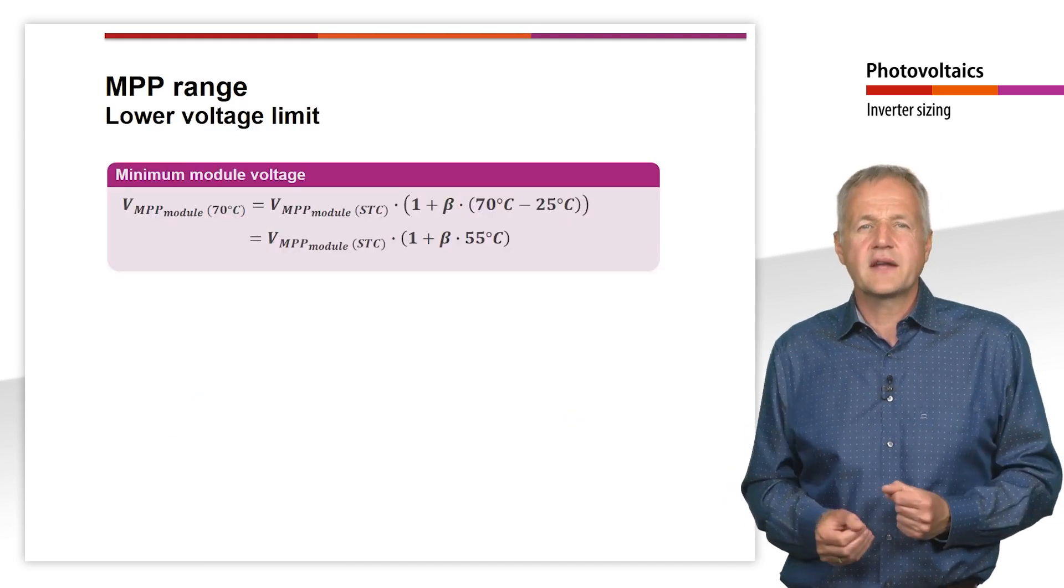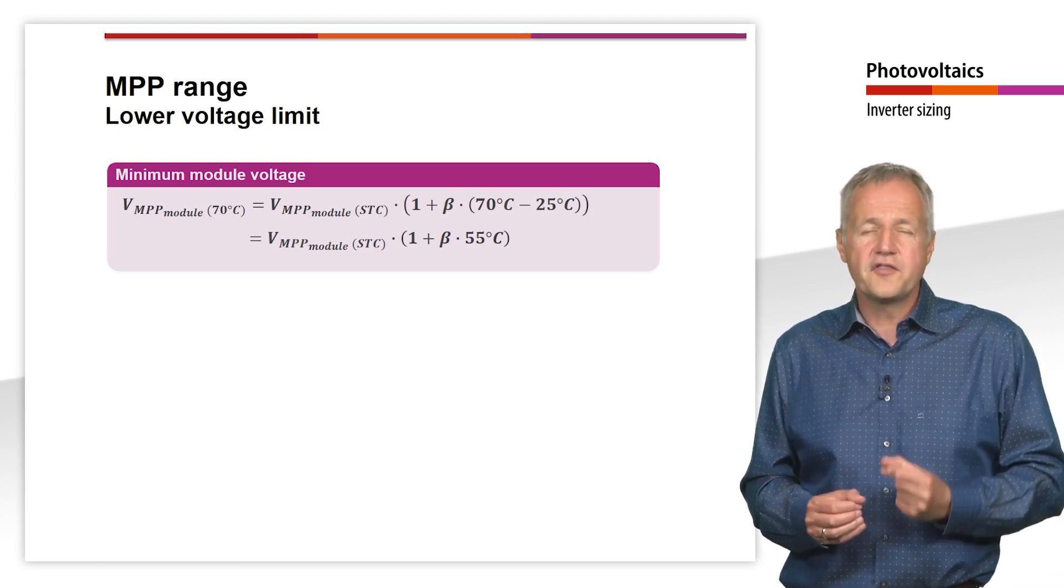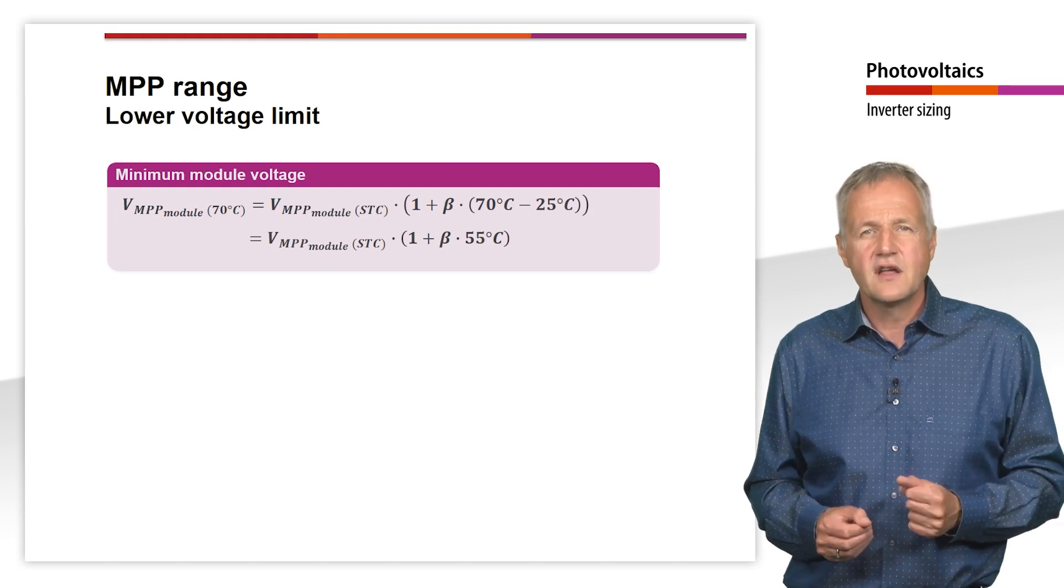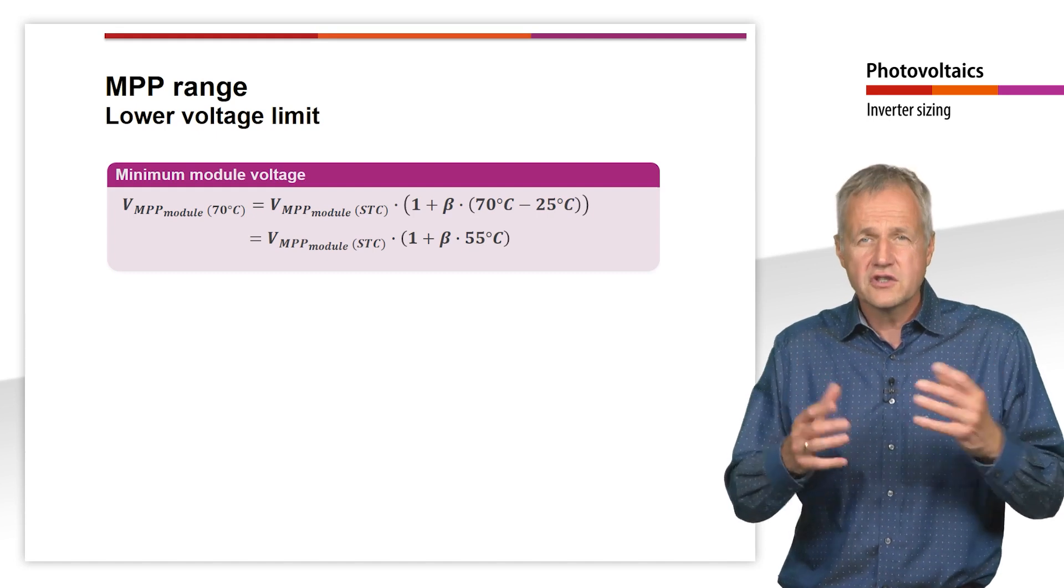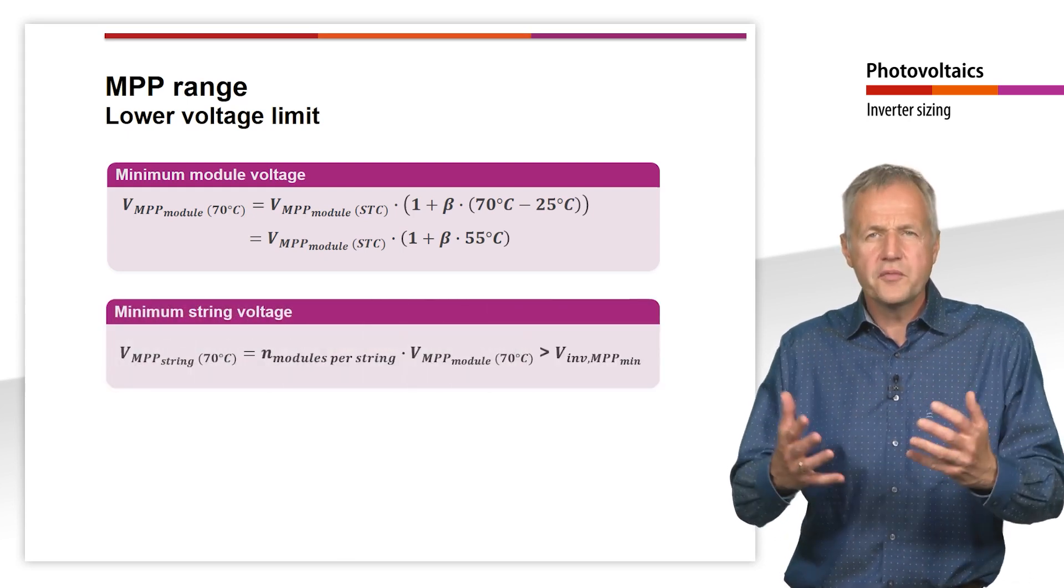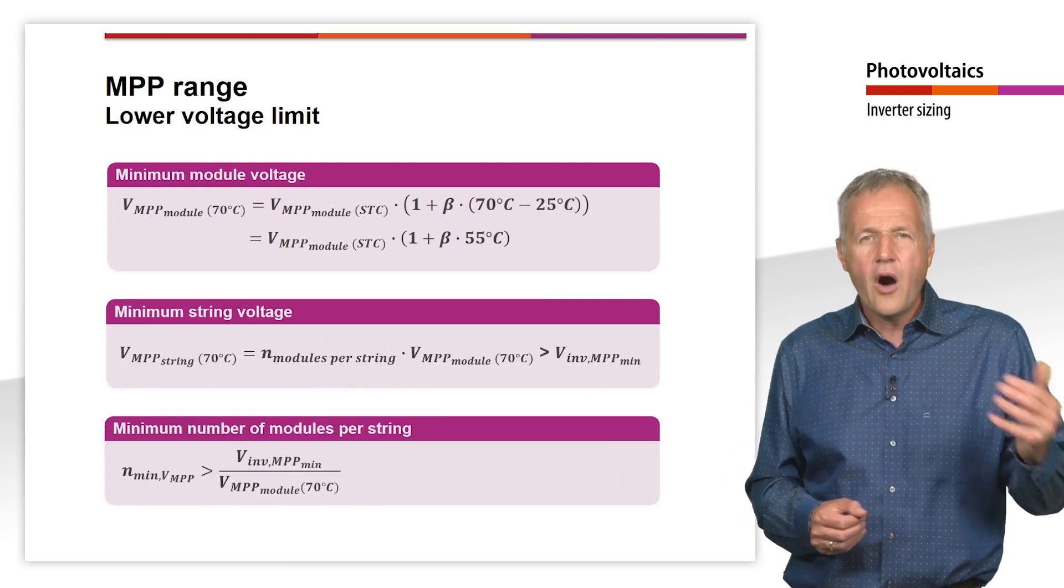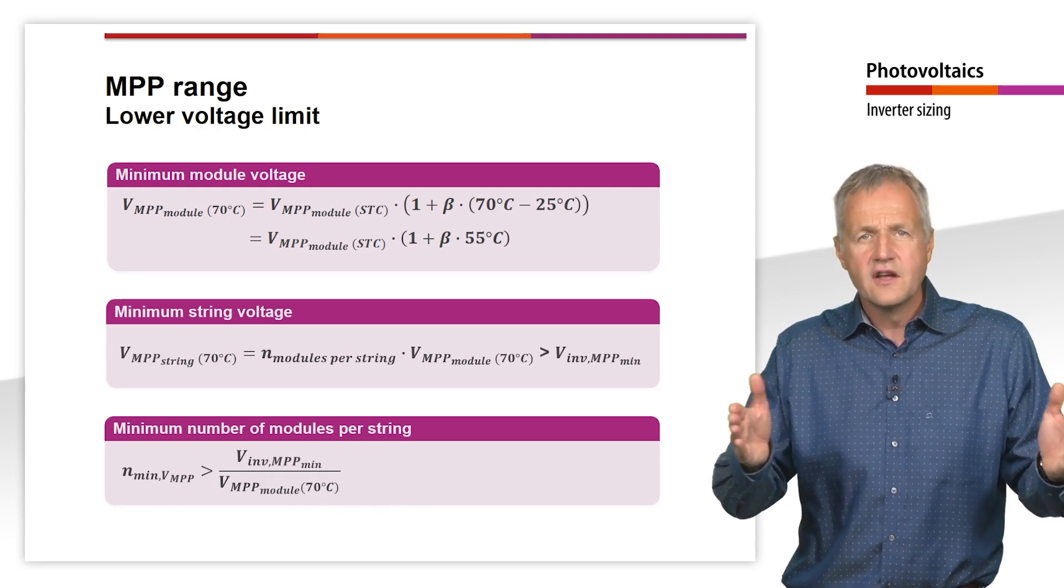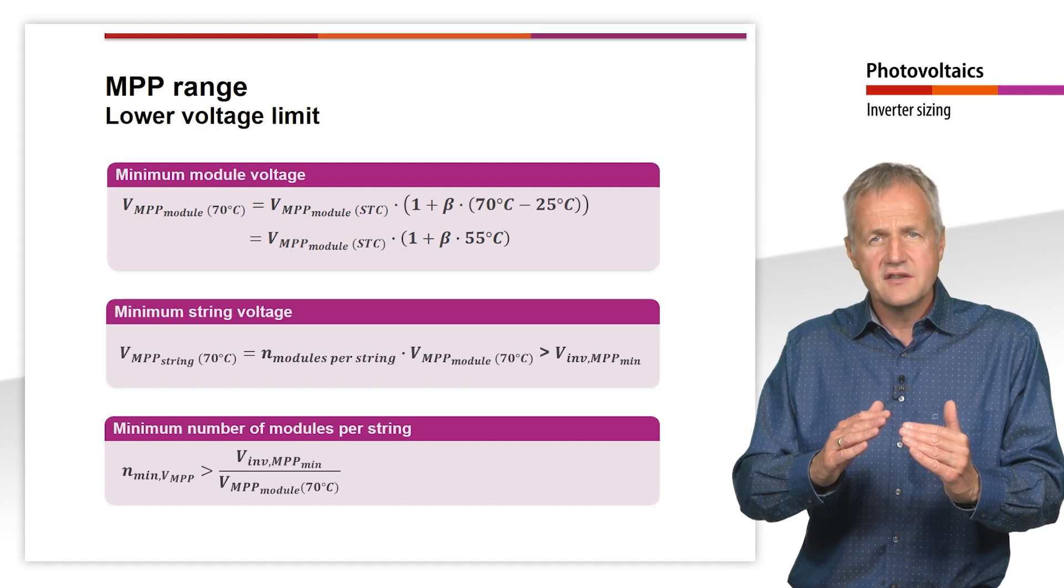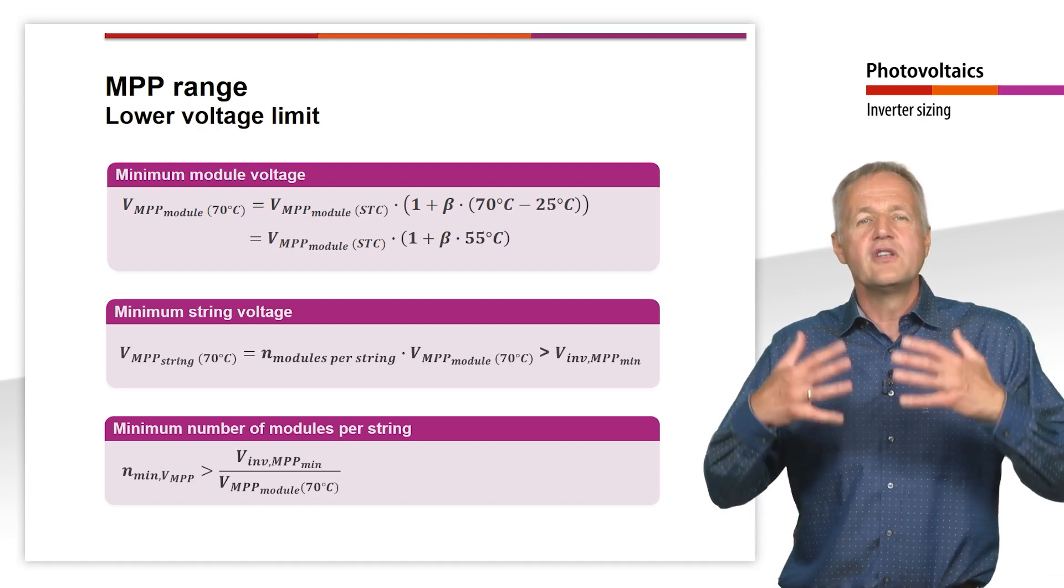In order to calculate the lowest expected MPP voltage for a specific solar module, we actually need the temperature coefficient of the MPP voltage. In most cases, however, this cannot be found in the datasheet. As an approximation, we can use the temperature coefficient of the open circuit voltage. From the minimum MPP module voltage, the minimum string voltage in the MPP can be calculated as before. If we want to calculate how many modules have to be connected in series to stay within the MPP range of the inverter, we calculate the quotient of the minimum MPP voltage of the inverter and the module voltage in the MPP. The number of modules must be larger than this quotient.